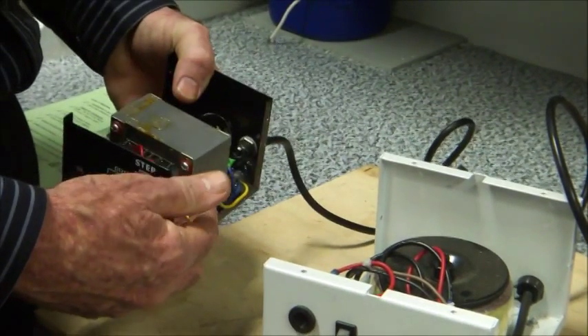I'll show you the wiring in here is very poor. It's got pieces of PVC wrapped around it. It's not really adequate. The leads are live here. If you look in here on the toroidal transformer, the leads are fully insulated with insulated quick connects all over it. Very solid earth to the ground and very clean wiring.